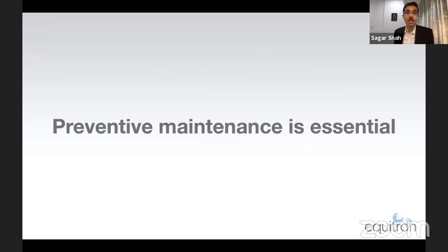Now, coming to the next point about preventive maintenance services. Have you checked whether you get preventive maintenance services from your autoclave vendor? The best way to prevent downtime is by having periodically scheduled preventive maintenance visits. A manufacturer or the local agent of the manufacturer can actually devise a plan for service, which will be based on your usage frequency and perhaps even the kind of loads that you're sterilizing. Because if they're more critical and if you would want more periodic, more regular services or preventive maintenance works, that's something that you would need to check with the local agent.